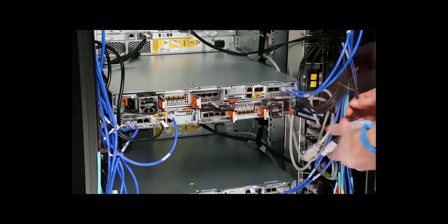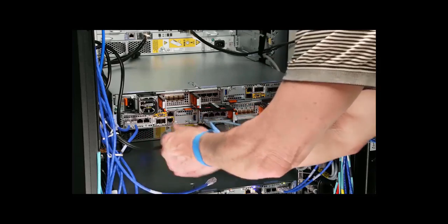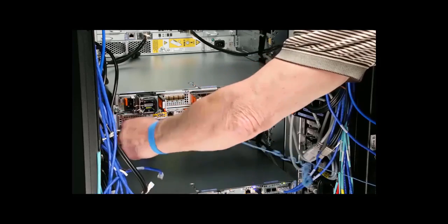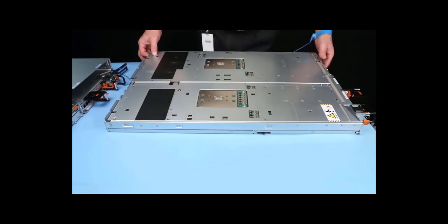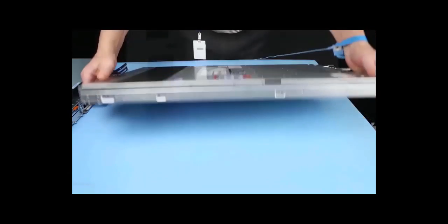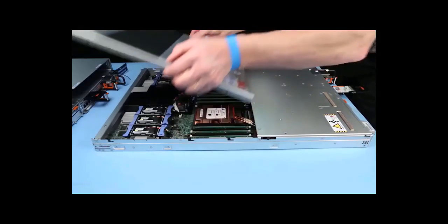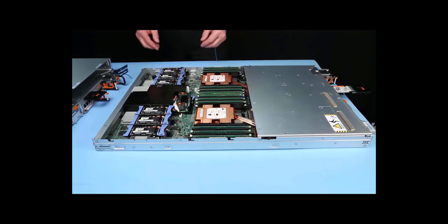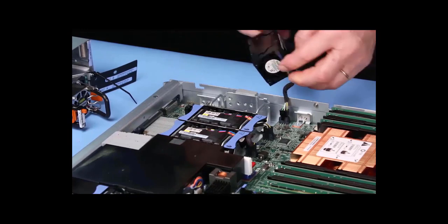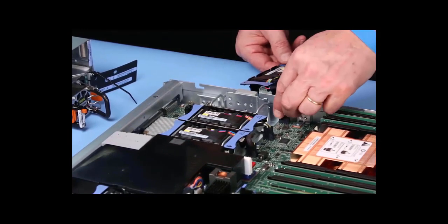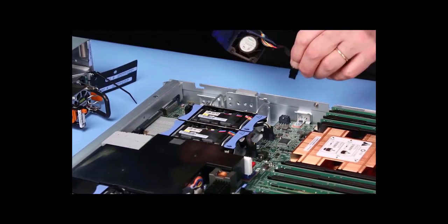So I'm going to look to uncable everything here. Again, for clarity, I'm just going to disconnect all the cables, but our issue is with the SPB. Make sure you mark those cables when you disconnect them all. And use your little blue handles. You have to push those in and slide that cover off, and then we want to locate the fan module in question here. So you can see that B0 is the first fan. It has a little connector to the motherboard. You have to go ahead and pull that off.